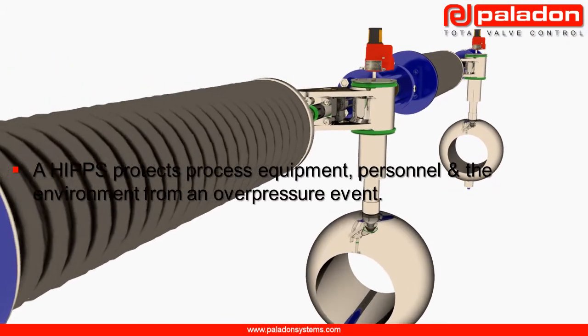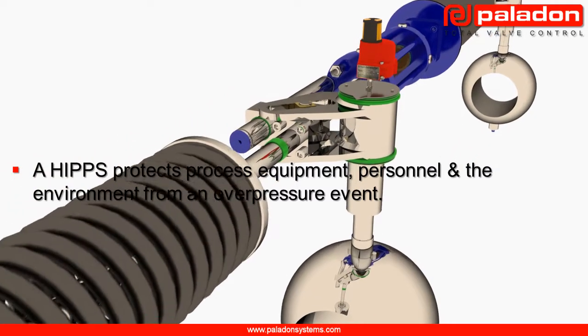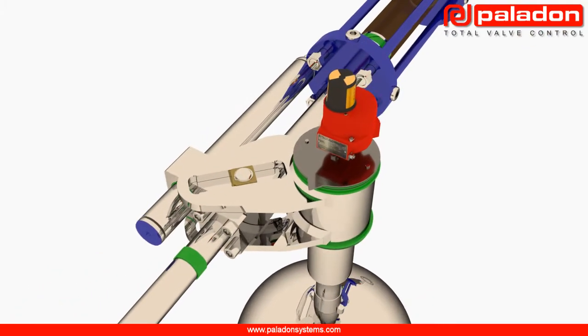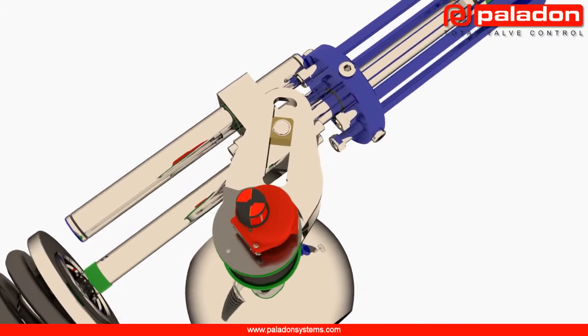Basically, a HIPPS protects downstream process equipment, personnel and the environment from an overpressure event. During an overpressure event, the HIPPS will sense increased upstream pressure and rapidly close block valves before any downstream process equipment can become over pressurised.